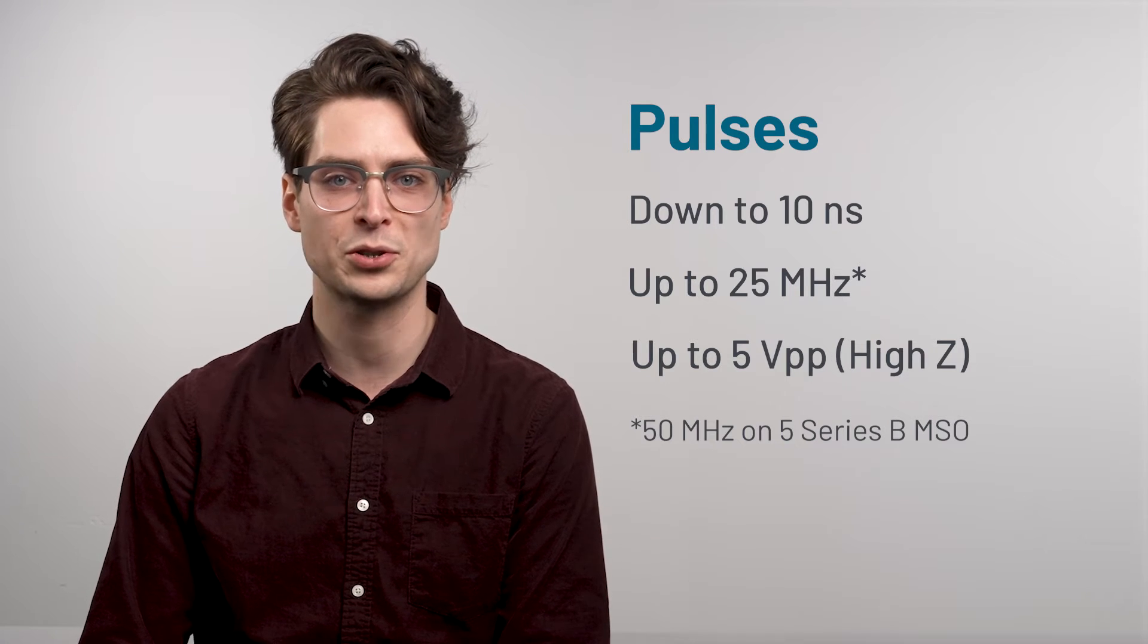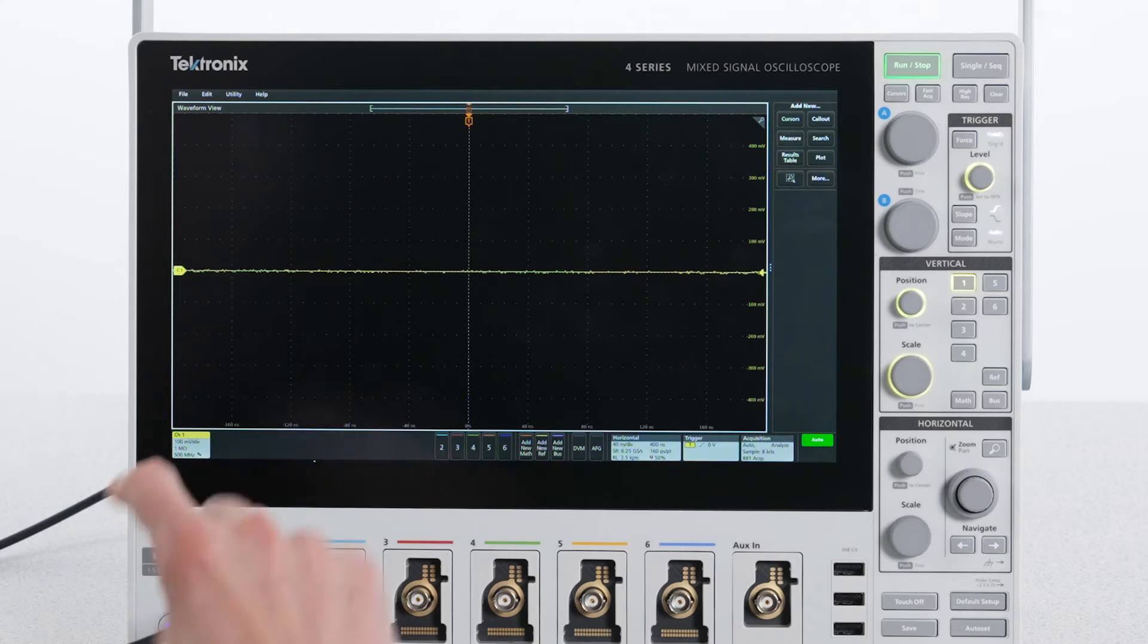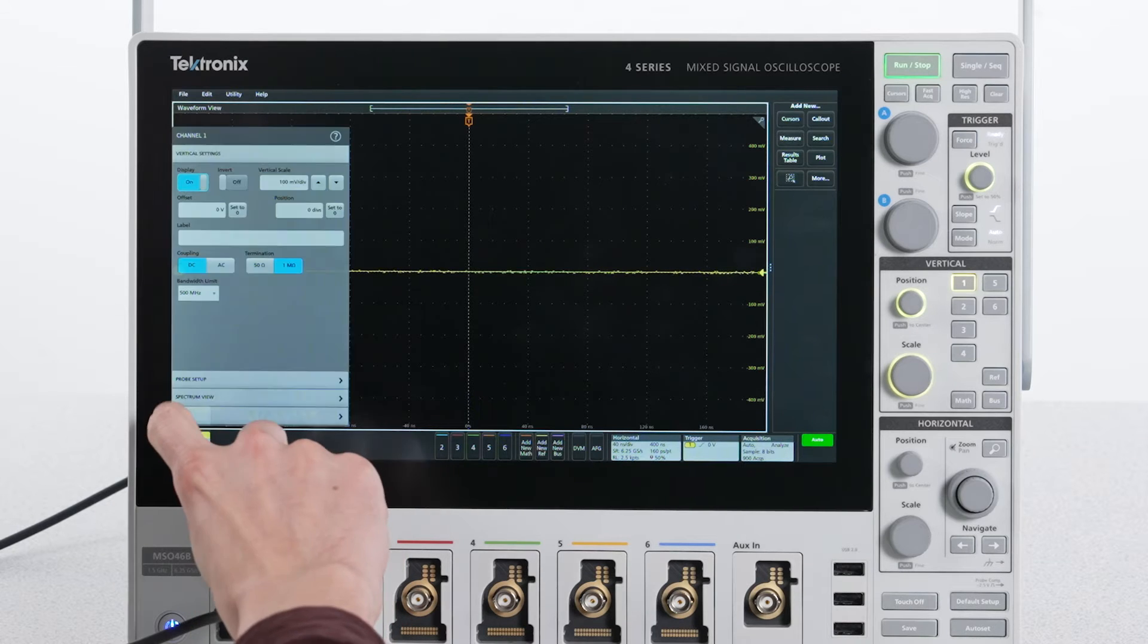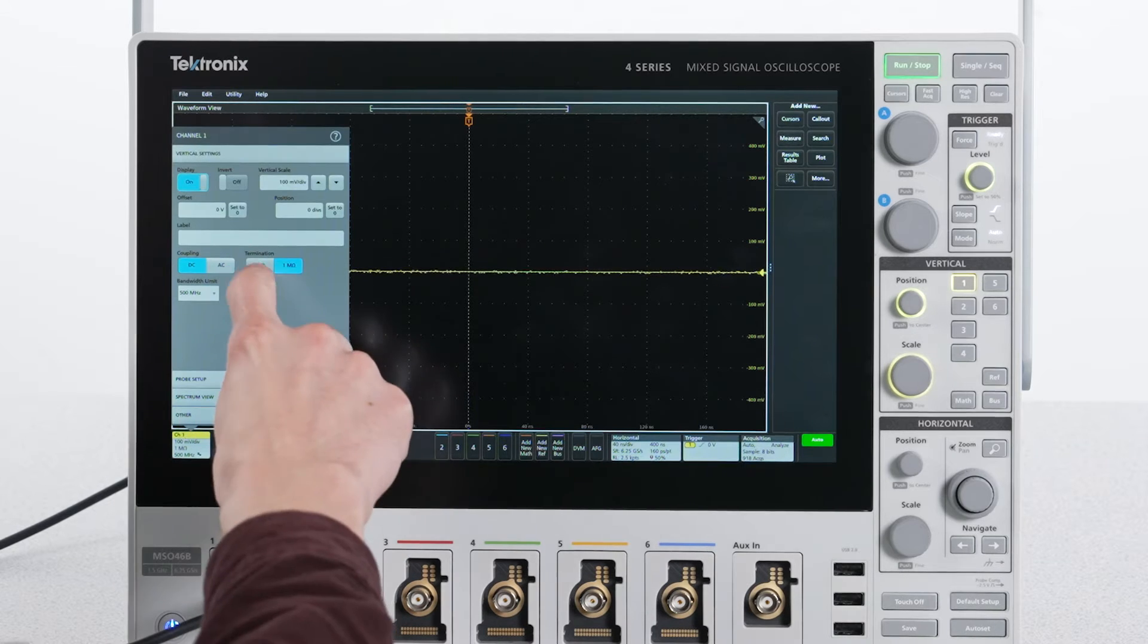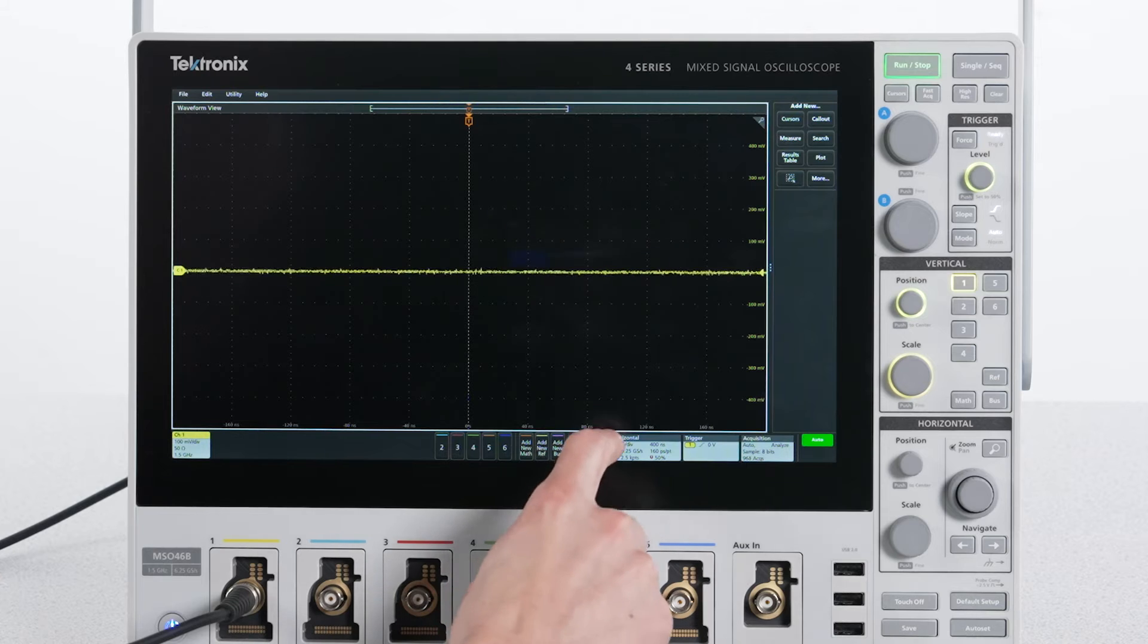Let's build a pulse train using the AFG. First, to match the AFG output, I'll set the scope's input impedance to 50 ohms. This will make the pulses cleaner.